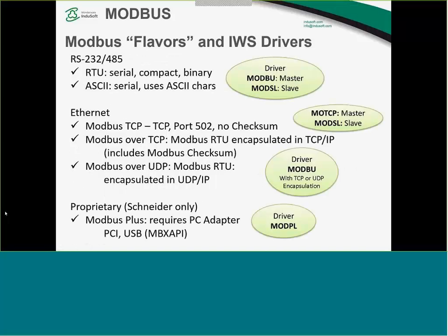So, talking a little bit about the Web Studio drivers that we have that speak Modbus. Through RS-232 or 485, RS-232 being single point and 485 a multi-point serial network, we have the MODBU driver for master and the MODSL driver for the slave. And we speak both the RTU and the ASCII modes on Modbus. So if you have a device and you want to speak Modbus, and you ask if InduSoft speaks that, yep. If you need a Modbus master, you're going to use the MODBU driver. If you need a Modbus slave, you're going to go to the MODSL.